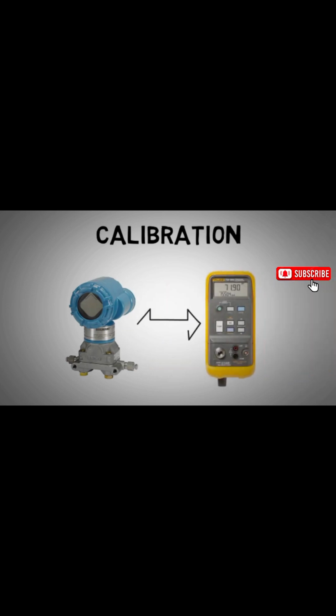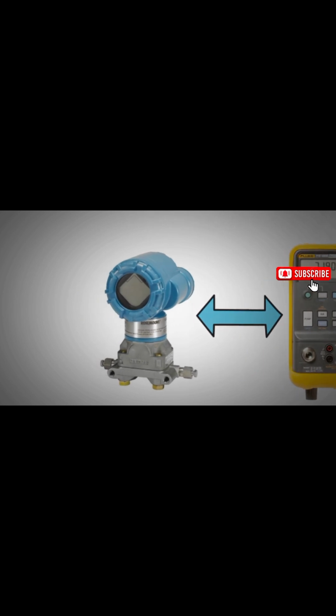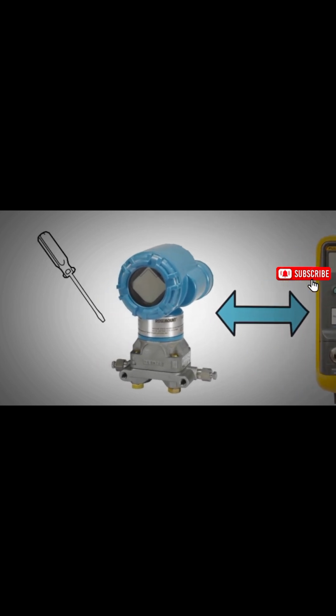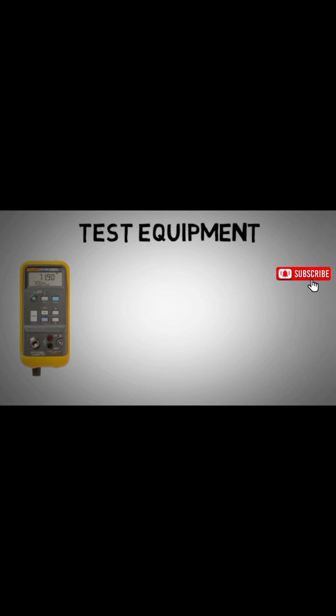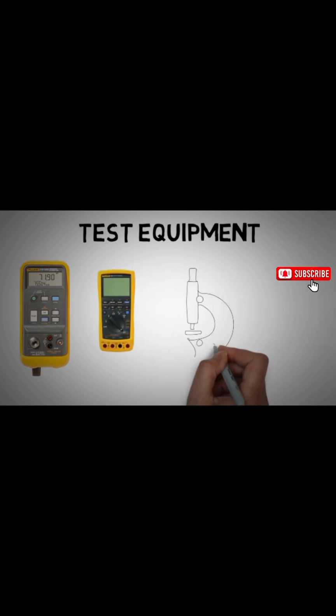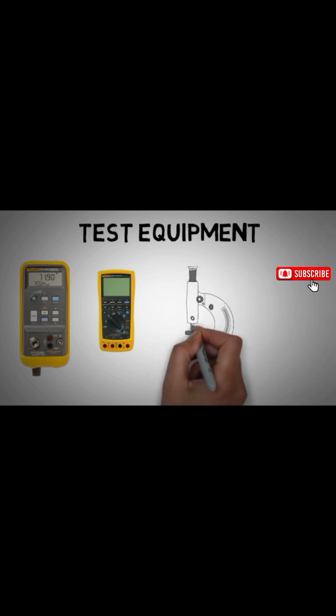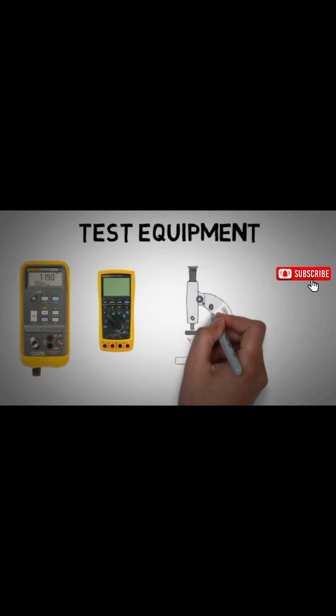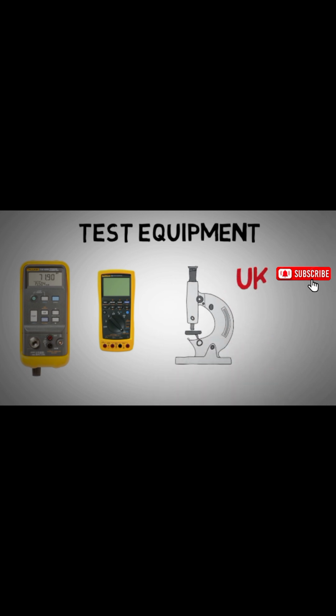Using a pressure transmitter as an example, which is monitoring the pressure in a vessel, if the pressure transmitter is not regularly calibrated, you will have readings that you cannot trust, often called fluctuated readings. How do you calibrate a pressure transmitter? The first thing you need to do is to know the test equipment you'll be using. And the next thing is to know the process and the procedures you'll be taking to calibrate these transmitters.